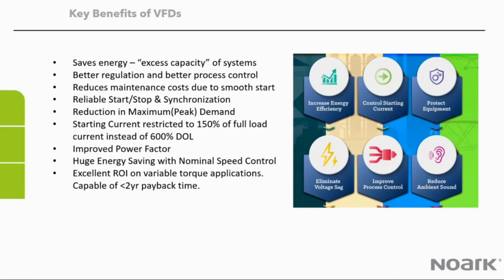Maintenance costs, as we talked about earlier, are reduced relative to smooth starting. You're not going with a starter from 0 to full speed in a heartbeat, which wreaks havoc on your mechanical stuff, your motor, and your line. Reliable start, stop, and synchronization. Reduced peak inrush demand as compared to starters and even soft starters. Soft starters are better, but they're not as low as a VFD. Starting current restricted to 150% of full load instead of 600% for direct across the line. And that's old data. Today with premium efficiency motors, I've measured it, it's 800 to 1200% inrush potential. With a drive, it's 150% only if we have to break a load free to get it up and moving, otherwise it's usually 100% or lower.